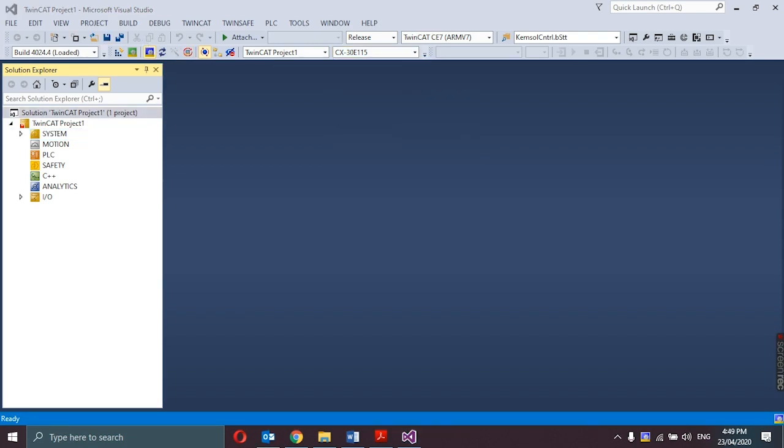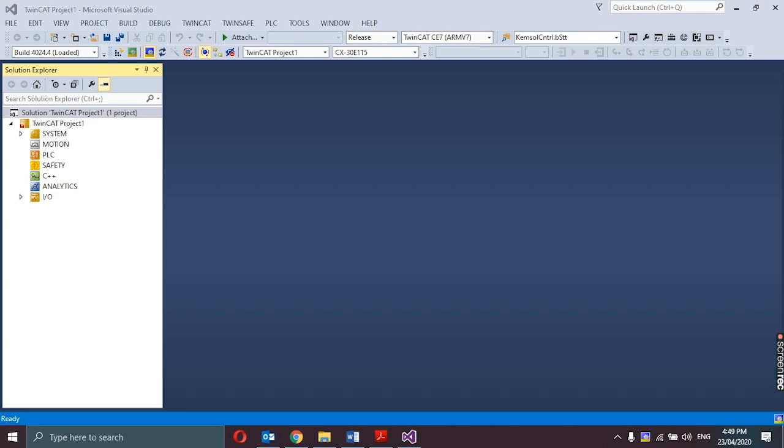Now that I have selected the appropriate target system, I can now proceed with the online device search or online scanning of the I.O. terminals. But take note that the online device search can only be used if the TwinCAT system is in config mode, blue TwinCAT icon or blue indication in the system manager. The online search is not available in run mode.